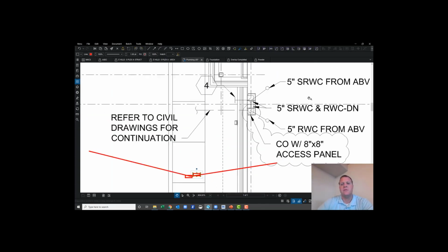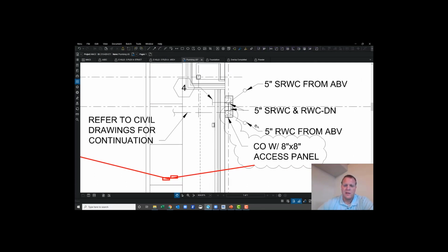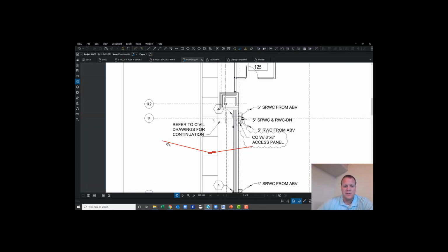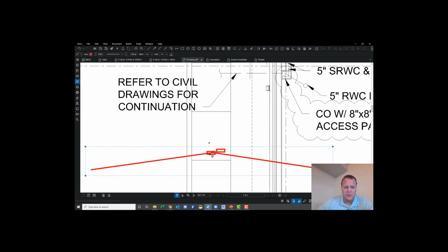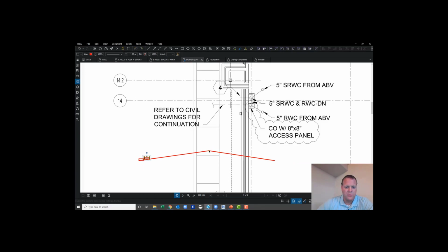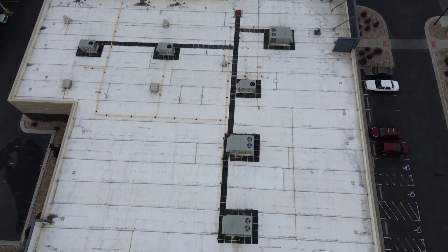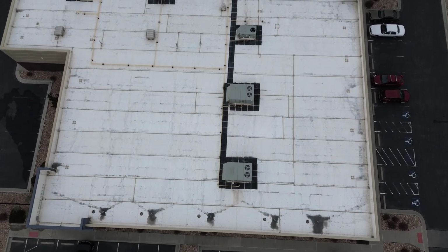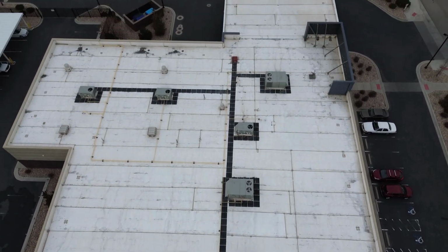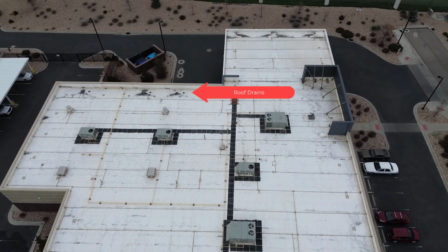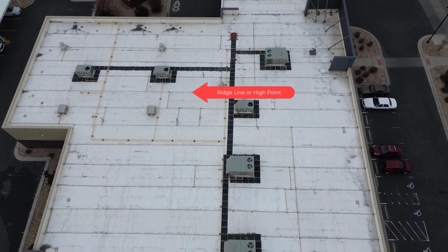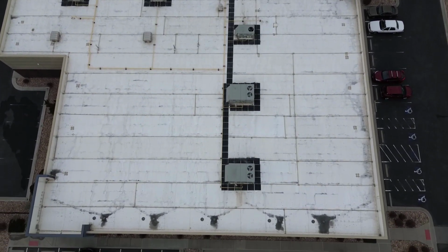And the difference is, we've got the roof drain here, we've got the secondary on this side, we've got the primary over here. So this roof drain's lower, it'd be this one, and this one would be higher. And it actually looks like I probably drew this incorrectly. The roof probably goes like this on this building. Even though it's still a low slope roof with a PVC or, my goodness, TPO roof, it's still low sloped, and it's probably towards the edge. Let's see. Yeah, this would be the ridge line, and it's sloping towards the edge of the building, just like that.